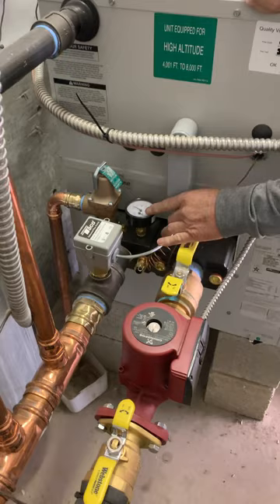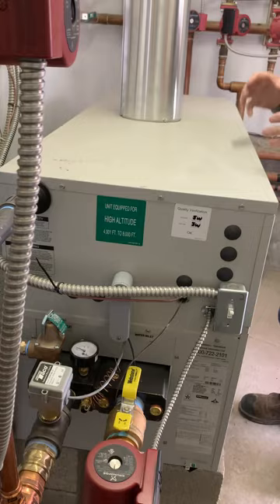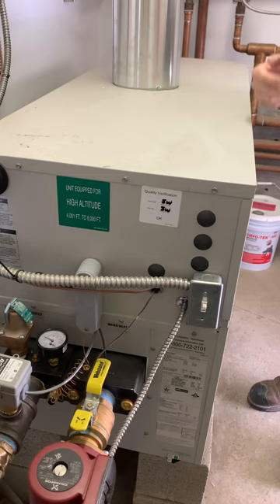The biggest thing you're going to have is glycol, how much pressure's in here. That's the blue gauge, and then add it if you need it. Right, and there should be some in here. Now, I'll mention that if we bought 4 different gauges and put them on here, they'd all read a little bit different. To get a good, accurate gauge, you spend quite a bit of money, but that'll give you an idea of what you got.